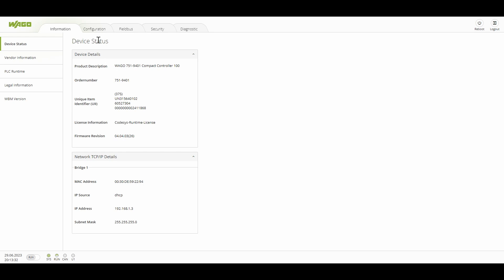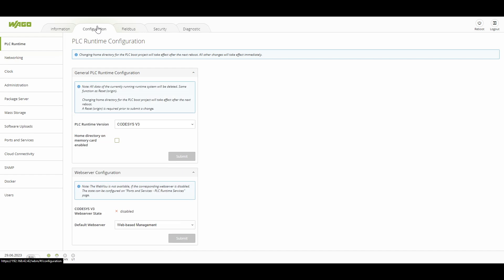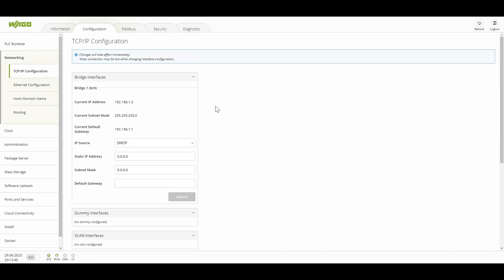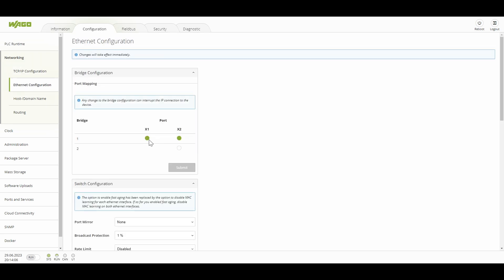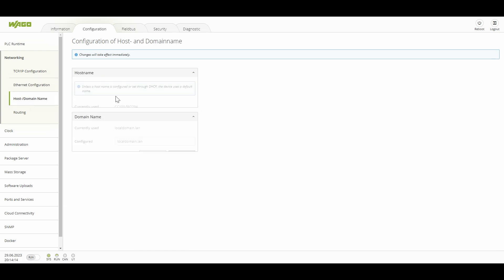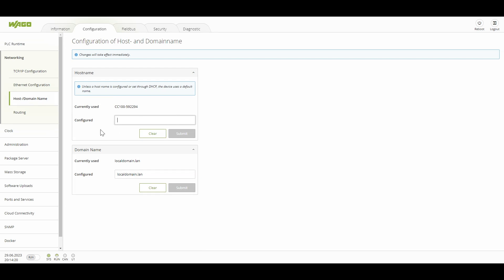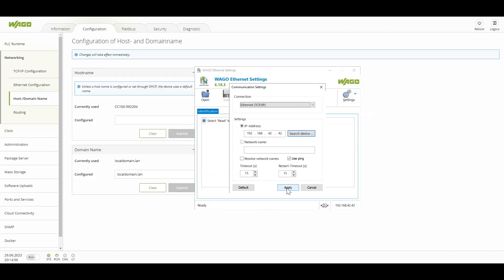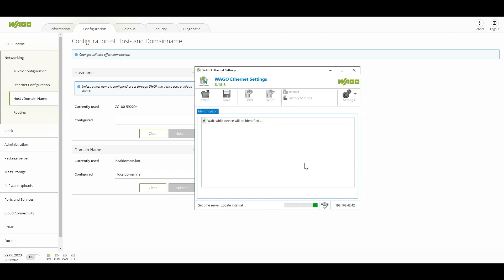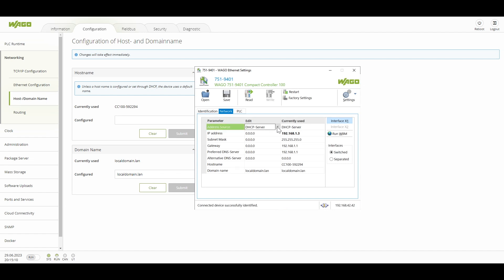This browser interface can also be used to configure different networking settings. Since I am connected via USB-C, we can configure the IP addresses of the system. It is currently set to DHCP, but we can set a static IP or anything else, and we can also make the ports switched or separated. We can also provide a hostname here. Alternatively, we can use the WAGO Ethernet Setting software to connect and configure these settings — so two options are available and we can use either one.